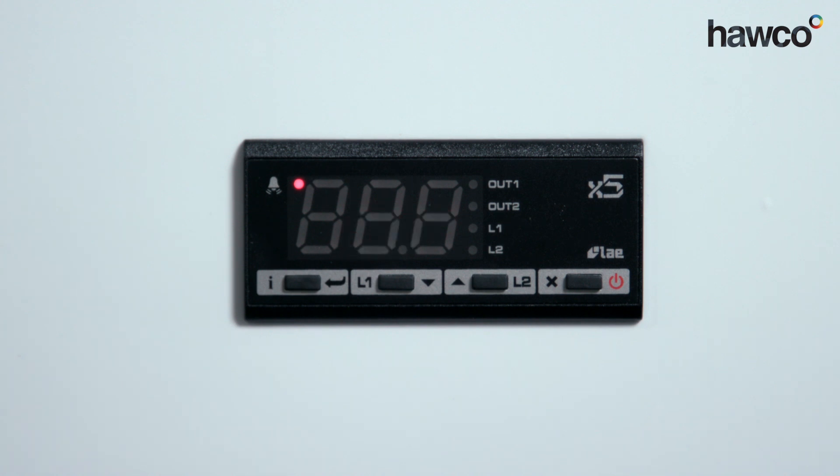Nine times out of ten, it means that the incorrect probe has been installed and not set up correctly. So in this instance, we've put in an NTC probe, so we need to make sure we go through the parameters to choose the NTC setup on the input.